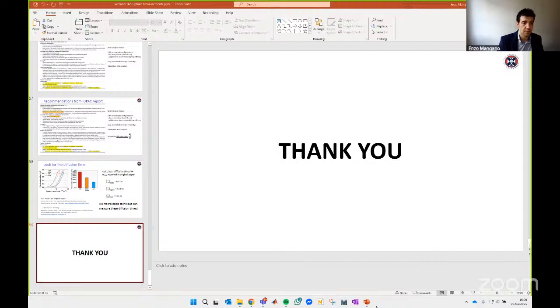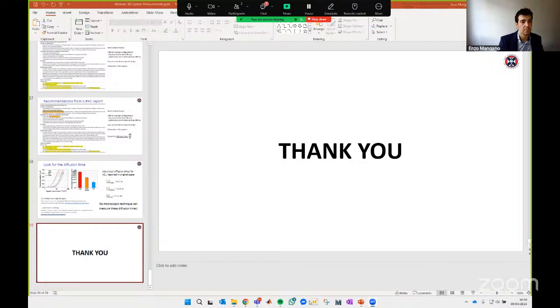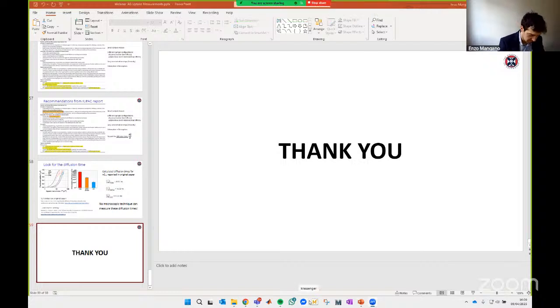Great, thank you very much. I think what you mentioned in that answer for the gravimetric systems and the time constant, and also what you mentioned earlier in your presentation, follows on pretty well to this question. Do you have any such recommendations for volumetric systems, or should someone just use the reduced pressure plot in those cases to identify too fast or too slow diffusion in the system?